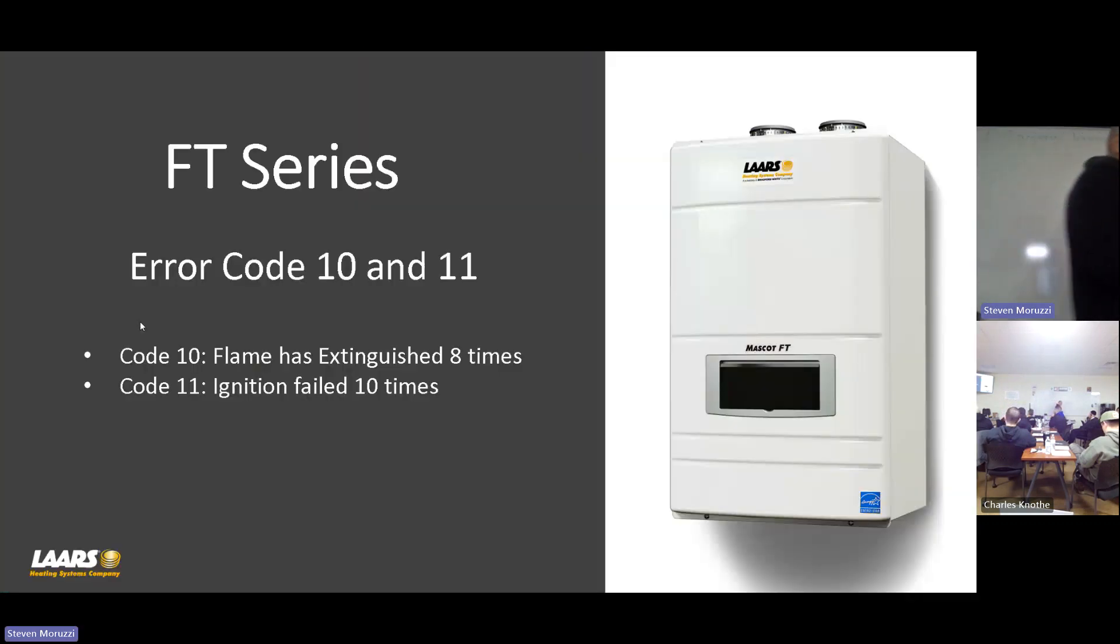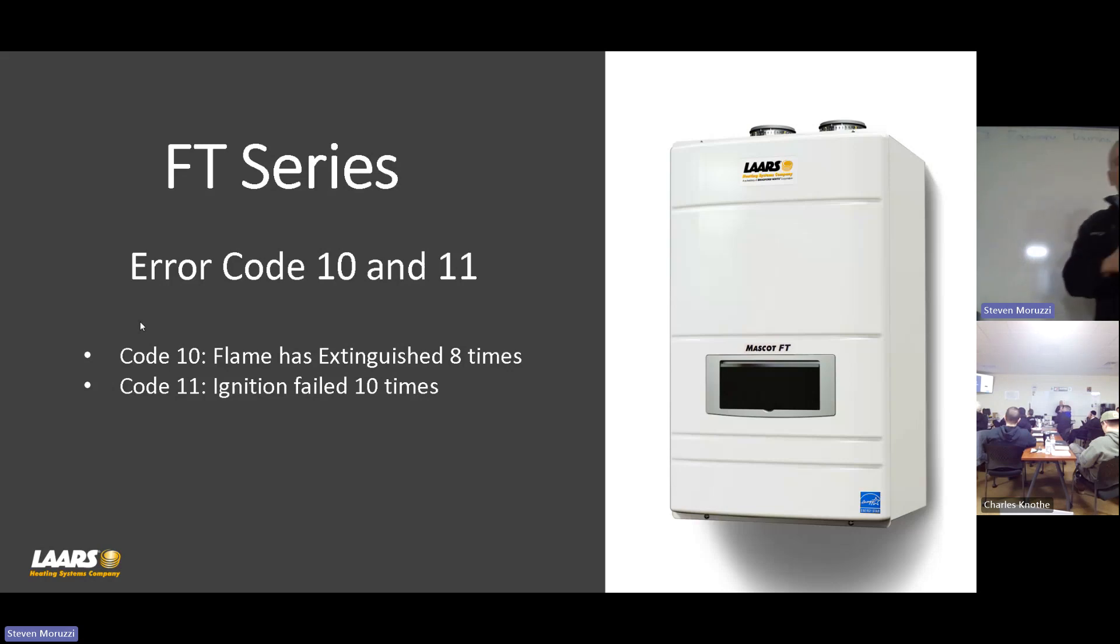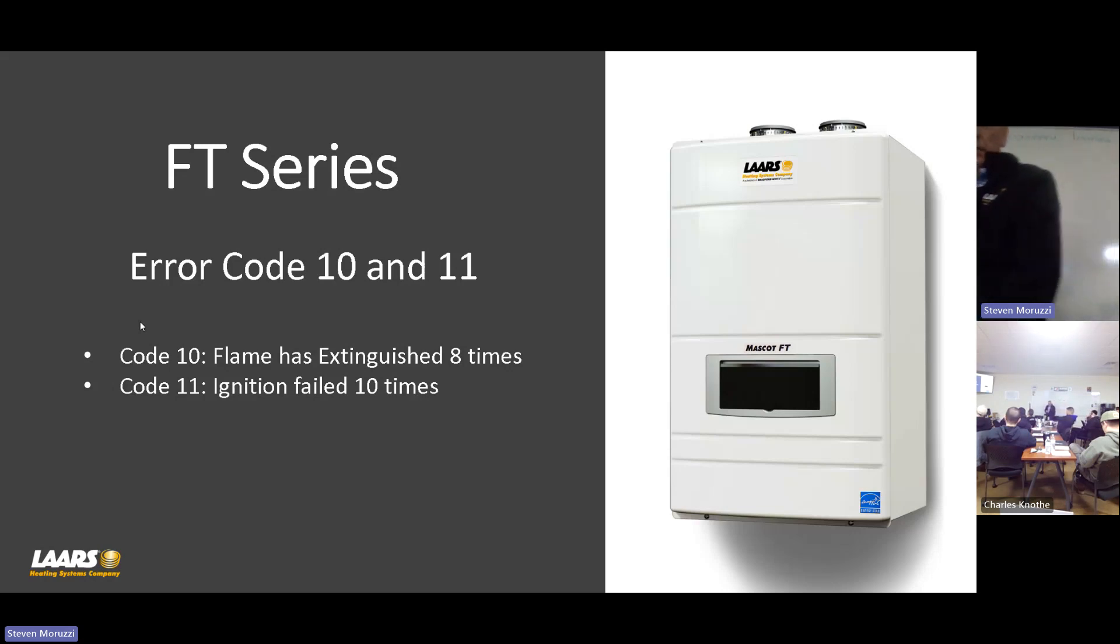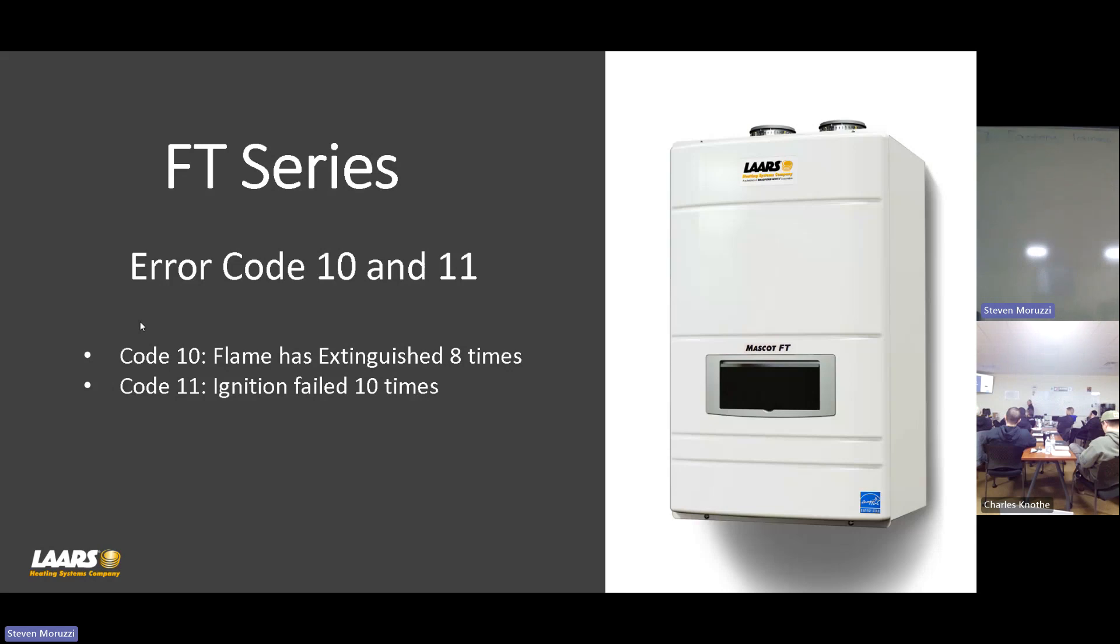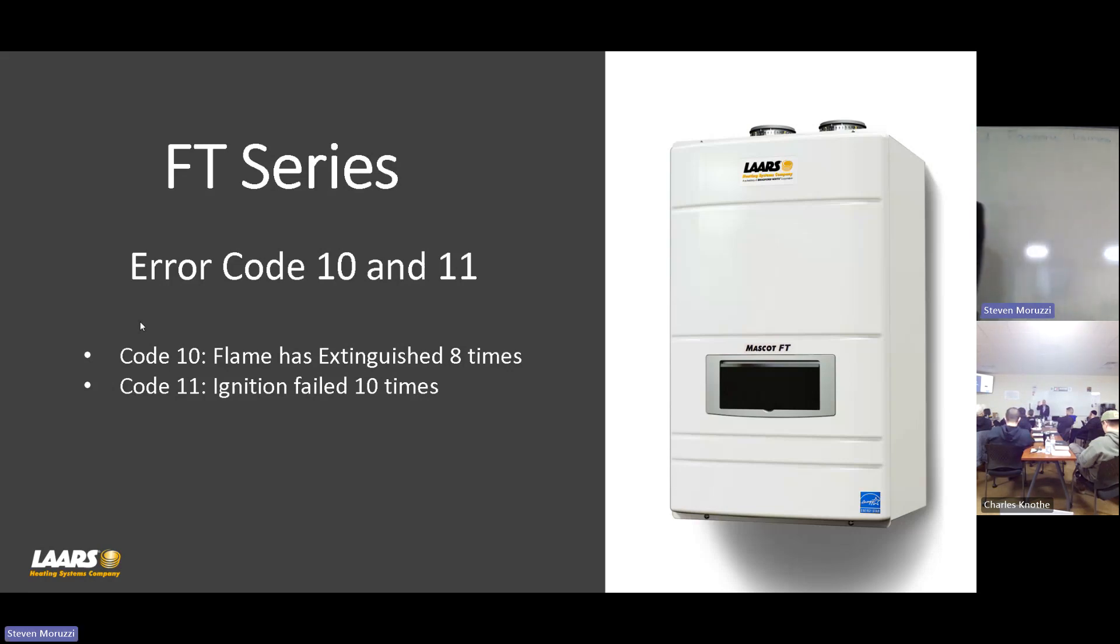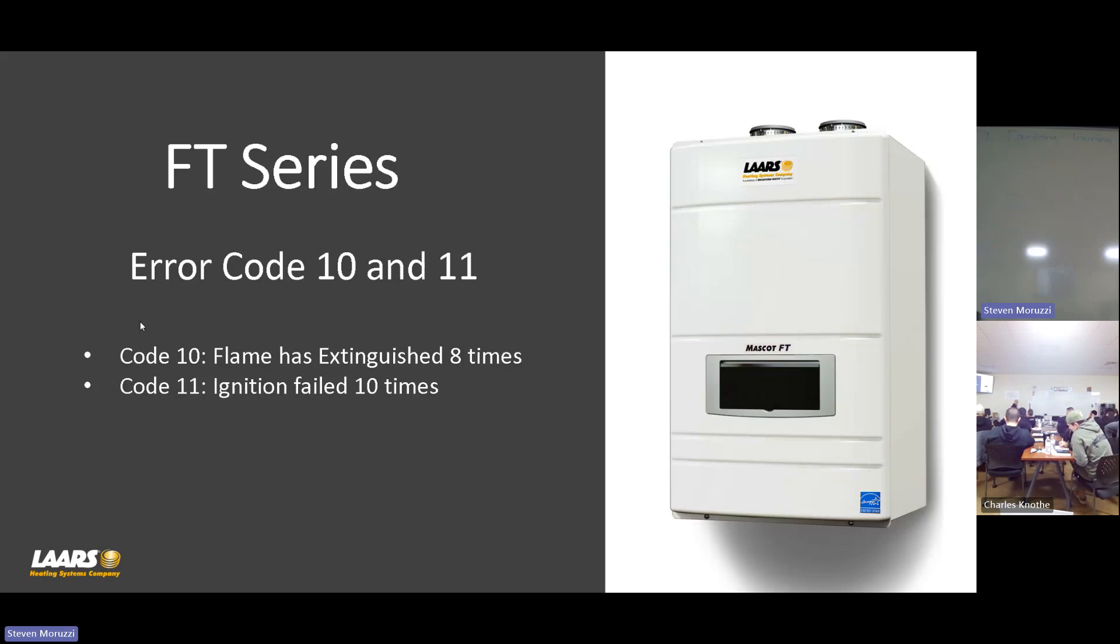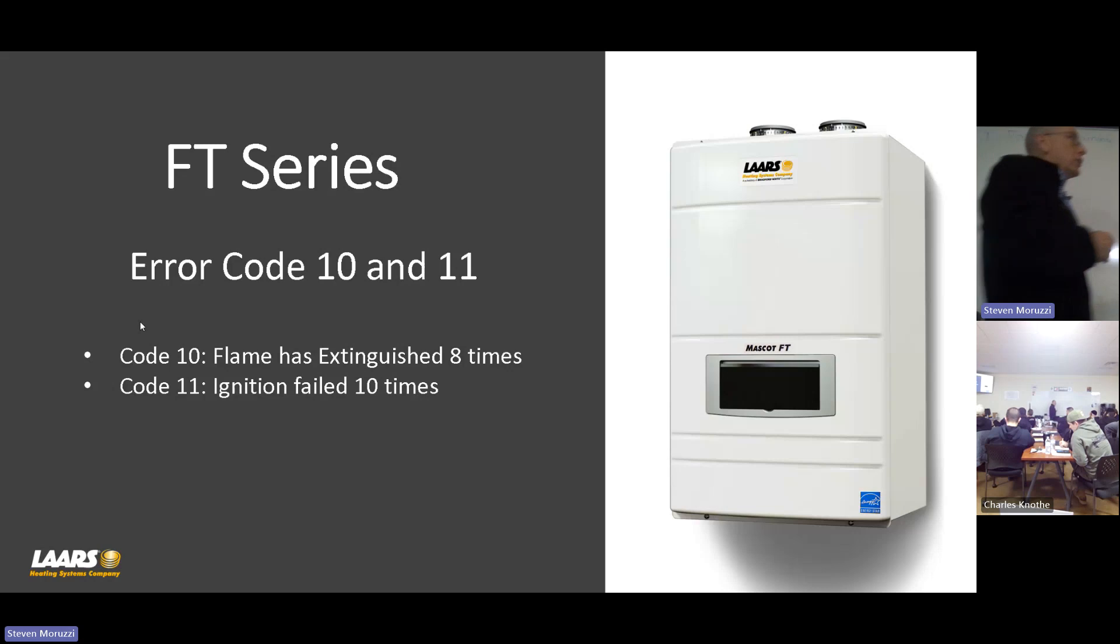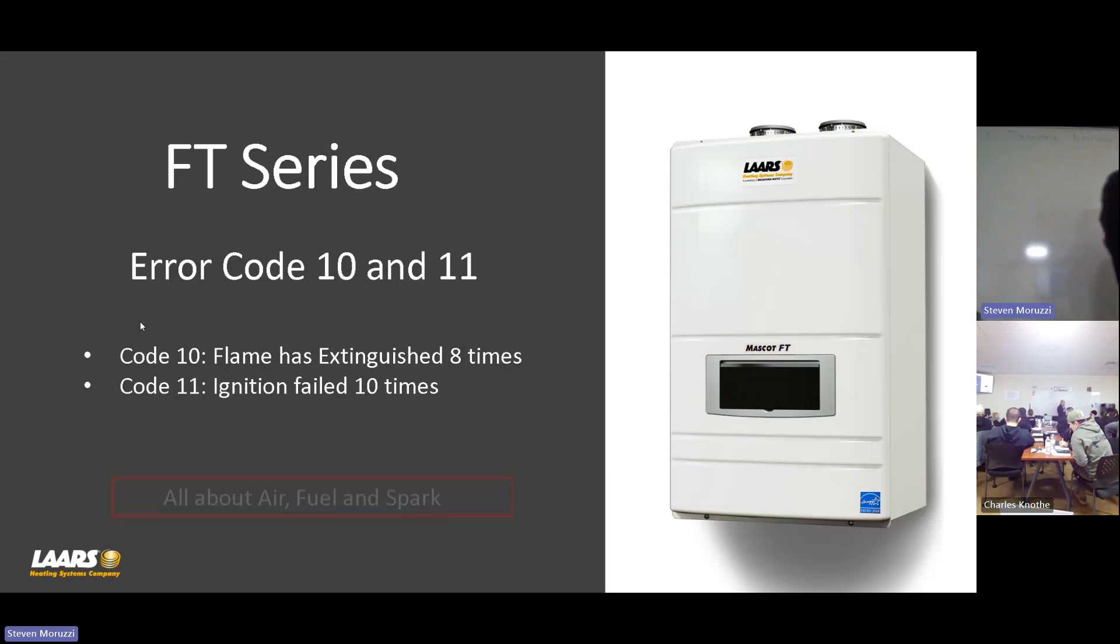Now let's talk about these error codes. Commonly, error code 10 and 11. Error code 10 is flame has extinguished eight times. Error code 11 is ignition failed ten times. So error code 10 means that we actually lit. The boiler lit under ignition, and then we lost flame. Error code 11 is it did not light. We give you multiple tries there on ignition failure.